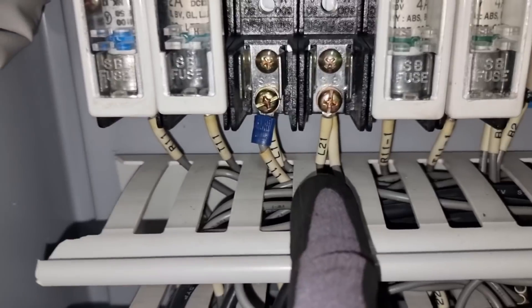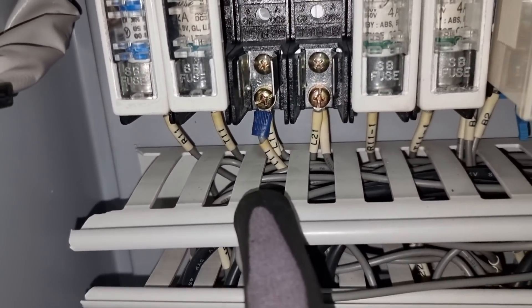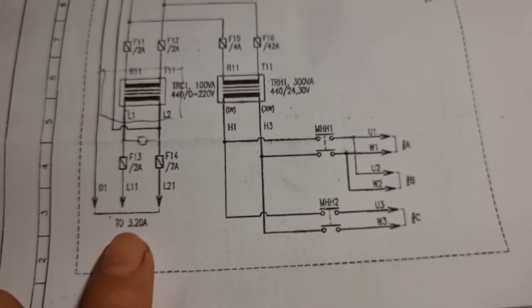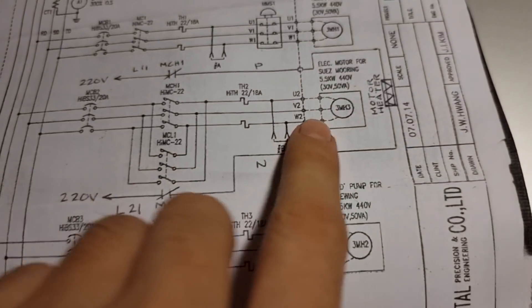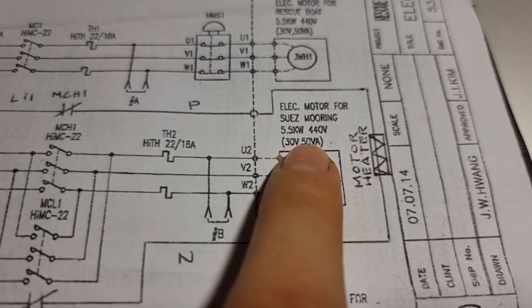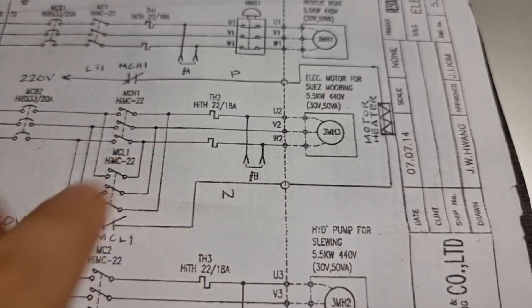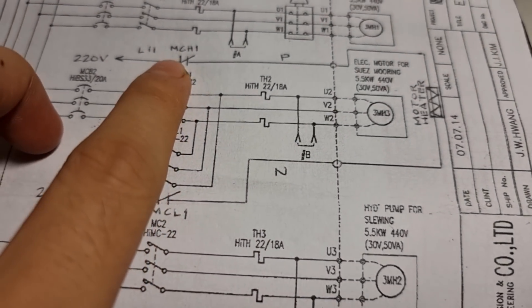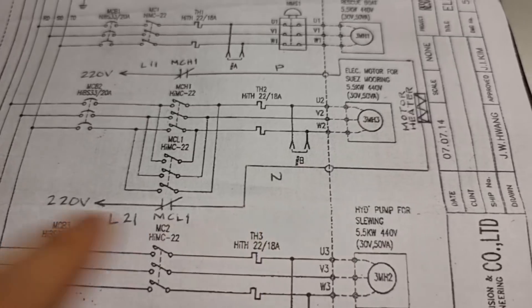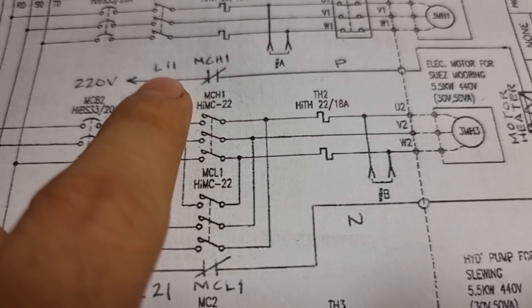After removing the fuses, I noticed plenty of lines connected on the output of the fuses. I reviewed the wiring diagram to check what these wires were. During the review, I noticed there was a modification done on the electrical motor for the Suez mooring — they had added an additional heater and connected it to MCL1 and MCH1.